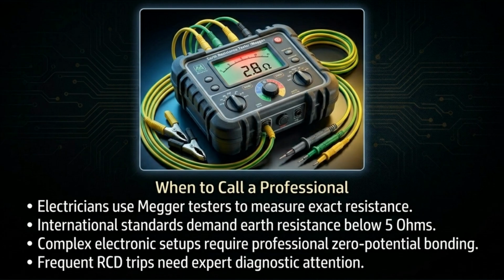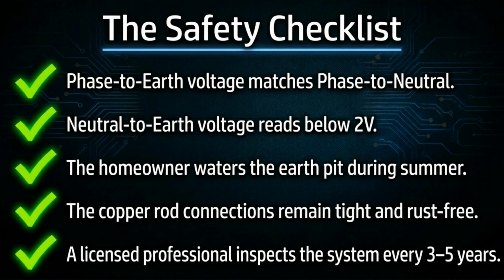Call a professional if your DIY tests indicate severe issues. Electricians use Megger testers to measure exact resistance, which should be below 5 ohms. Also, seek help for complex setups or frequent RCD trips. Remember this safety checklist. Ensure phase to earth matches phase to neutral, and neutral to earth is below 2V. Maintain the pit, keep connections clean, and have a professional inspect the system every 3 to 5 years.